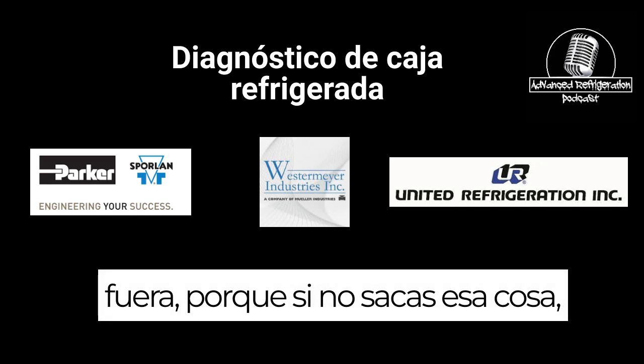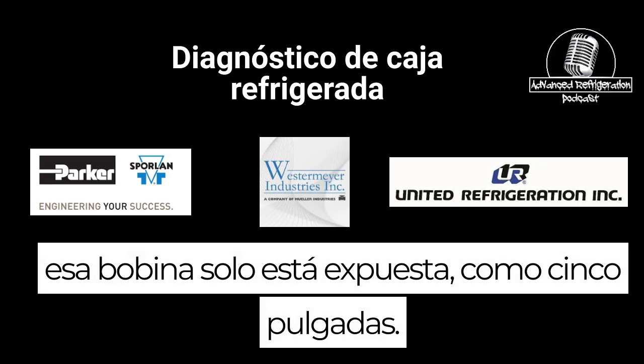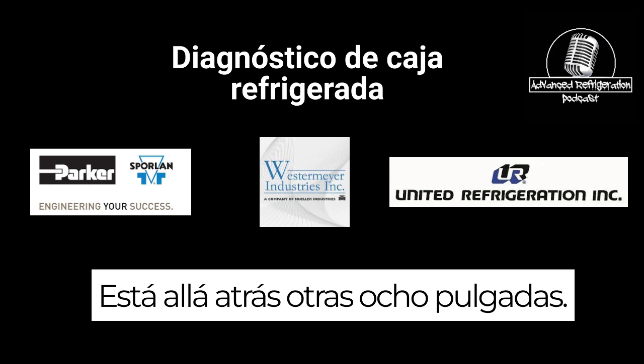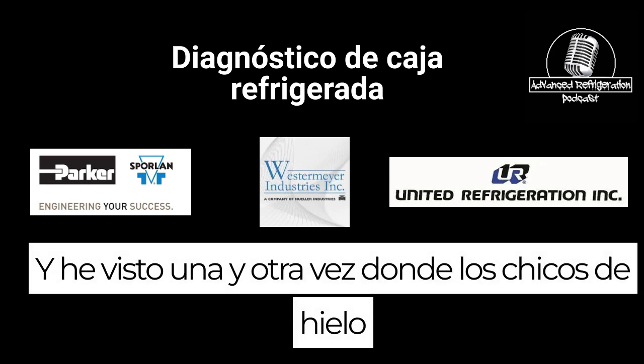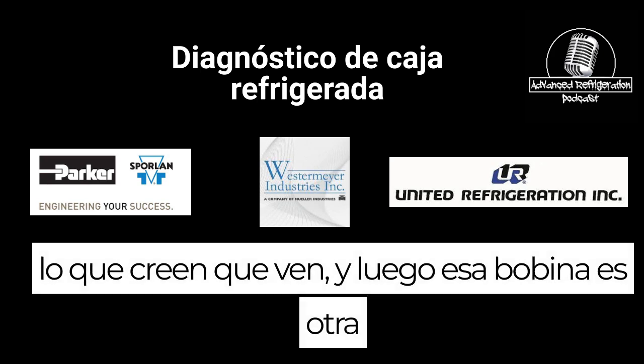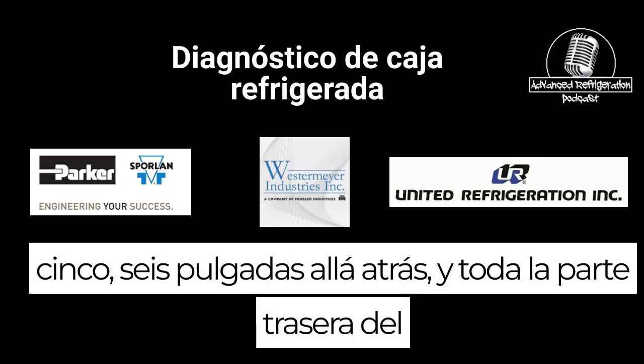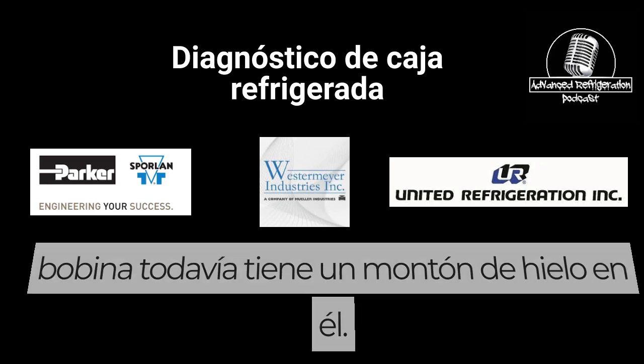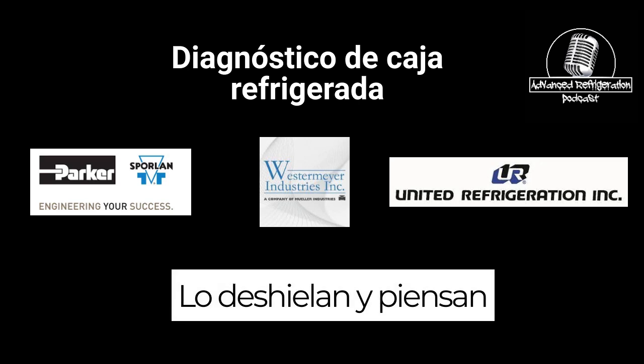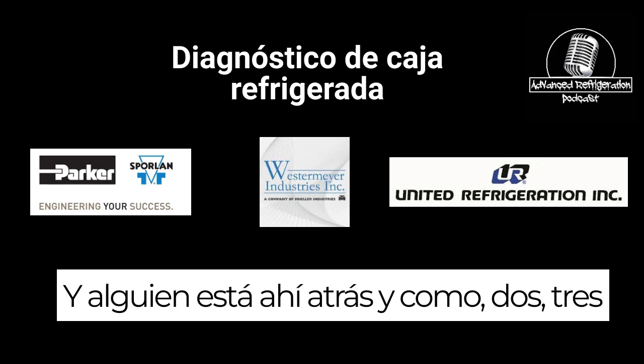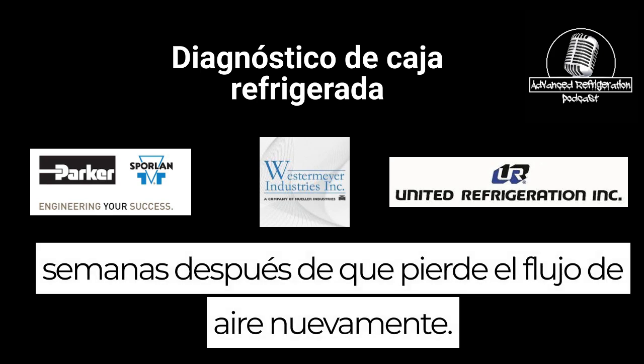Because if you don't pull that thing off, that coil is only exposed like 5 inches. It's back there another 8 inches. And I've seen time and time again where guys de-ice what they think they see, and then that coil's another 5, 6 inches back there, and the whole backside of the coil still has a bunch of ice on it. They de-ice it and think everything's fine, and they leave, and somebody's back there like 2, 3 weeks later after it loses airflow again.